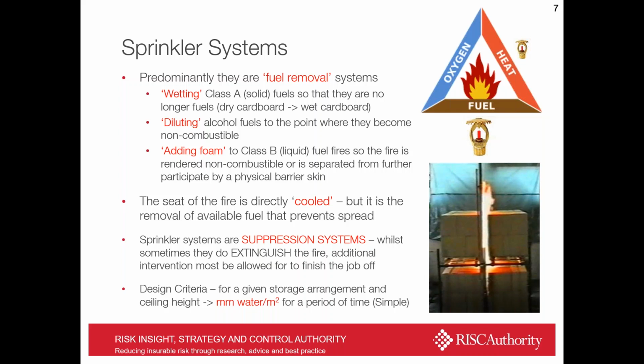additional chemicals can be added to the water entering the sprinkler system, such as firefighting foams, which essentially will render the fuels non-combustible or separate them from further participation in the fire by a physical barrier or a skin or a frothy layer, if you like. Now, obviously, they do remove heat as well from the seat of the fire directly, but really it's common practice that for sprinklers, the area will burn out where the fire initiates because you've made the surrounding product non-combustible by the flow of water over it or the absorption of water into it.